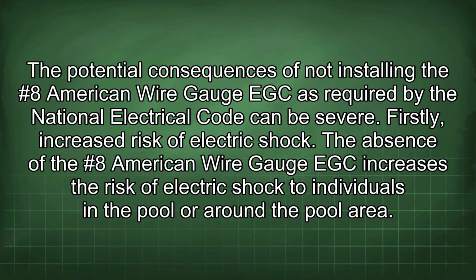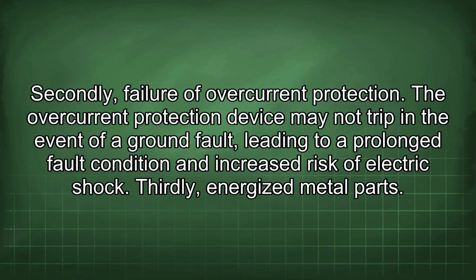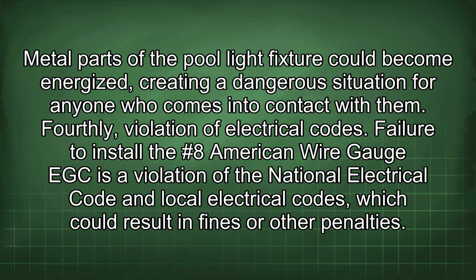The potential consequences of not installing the #8 American wire gauge EGC as required by the National Electrical Code can be severe. Firstly, increased risk of electric shock. The absence of the #8 American wire gauge EGC increases the risk of electric shock to individuals in the pool or around the pool area. Secondly, failure of overcurrent protection. The overcurrent protection device may not trip in the event of a ground fault, leading to a prolonged fault condition and increased risk of electric shock. Thirdly, energized metal parts. Metal parts of the pool light fixture could become energized, creating a dangerous situation for anyone who comes into contact with them.